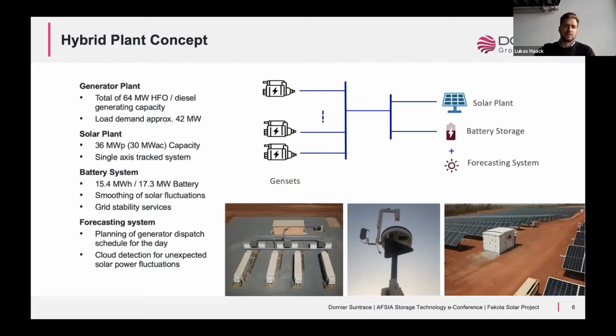The load of approximately 42 megawatts requires constant power supply on a 24/7 basis, as I explained. The optimal size we came up with is a solar plant of 36 megawatt peak and 30 megawatt AC capacity. It's a single axis tracked system, and it includes a battery system of 15.4 megawatt hours and 17.3 megawatts of battery power. It also includes a forecasting system that predicts the solar power to be expected on a day-ahead basis.